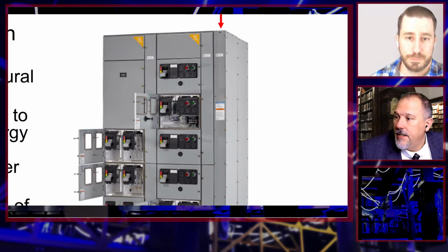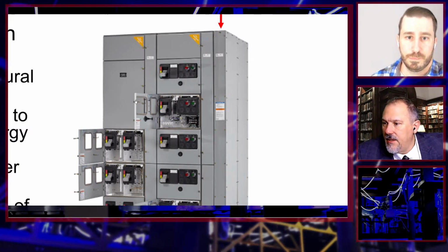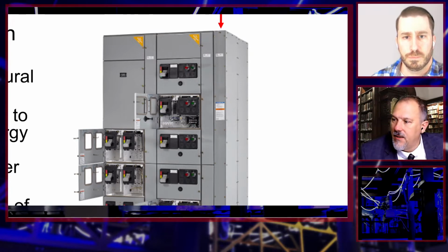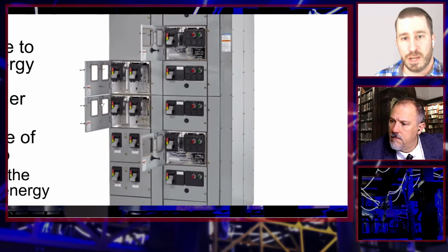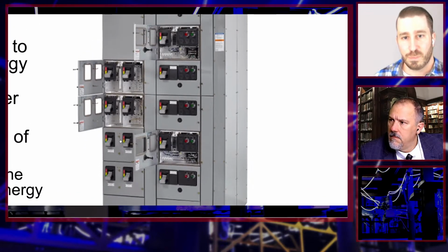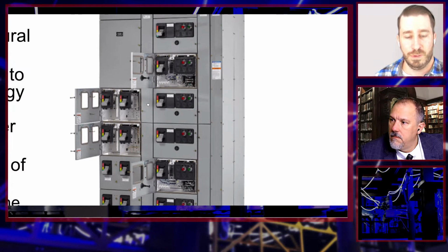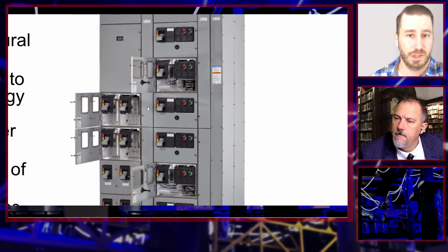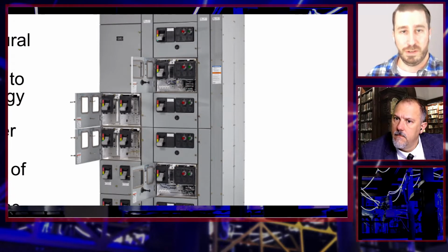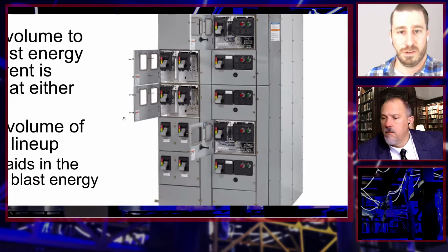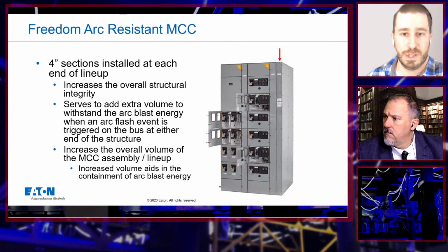Now, I don't see those big rubber gaskets around this bucket. Why is that? Fortunately, in our testing, we've got some rubber gaskets you'll see a little bit there, but as you can imagine, a motor control center bucket is pretty confined space, and with the addition of the latches and things like that, this is again the design of the equipment varies by manufacturer and even with the type of equipment.